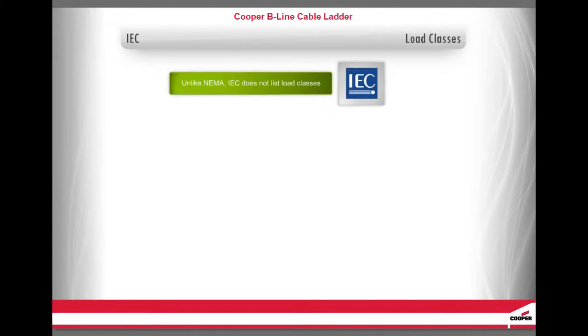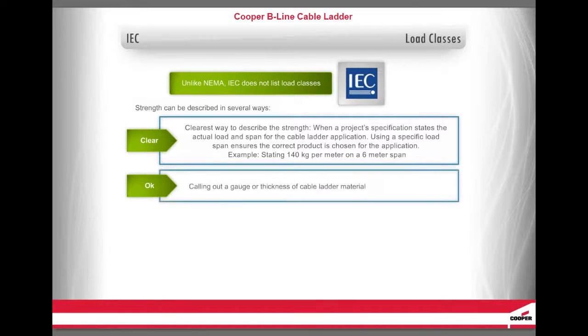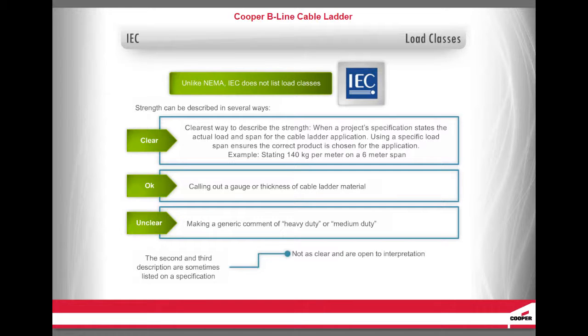Unlike NEMA, IEC does not list load classes. In the IEC specifications, the strength can be described in several ways. First, the clearest way is when the project specification states the actual load and span for the cable ladder application — for example, stating 140 kilograms per meter on a 6-meter span. Second, calling out a gauge or thickness of the cable ladder material. Third, making a generic comment such as heavy-duty or medium-duty, which is unclear and open to interpretation. In this situation, it would be best to contact the project specifier to gain additional information.